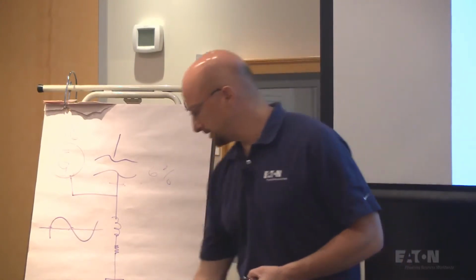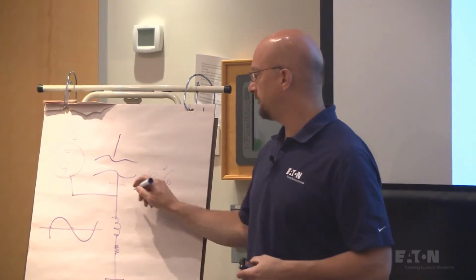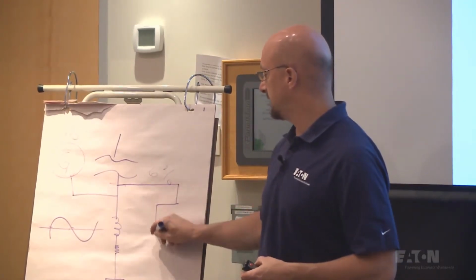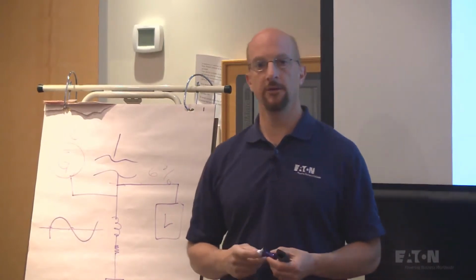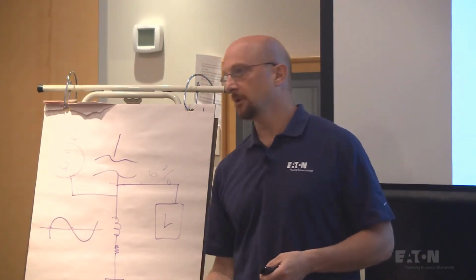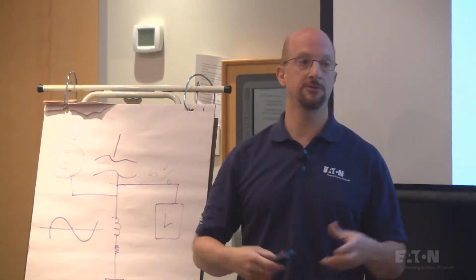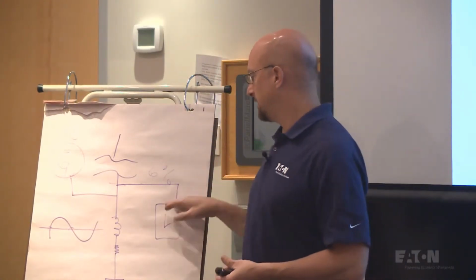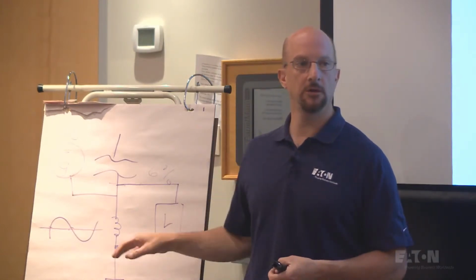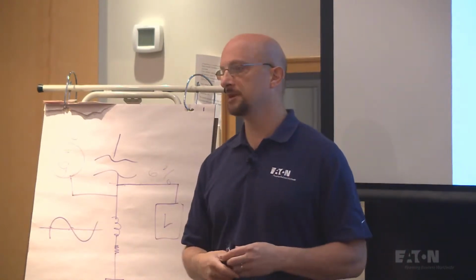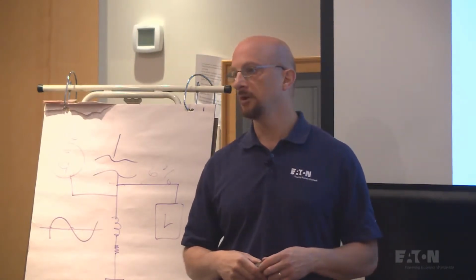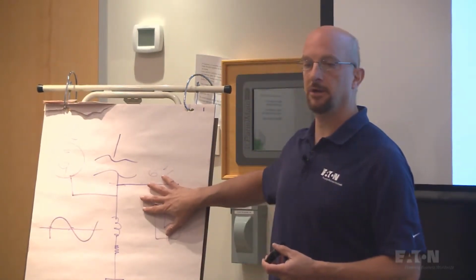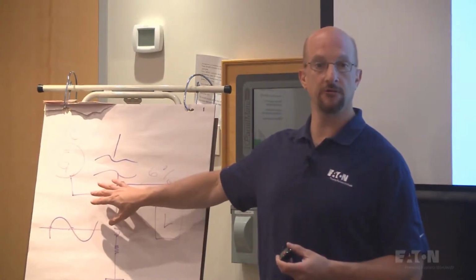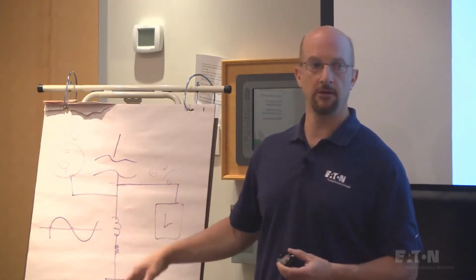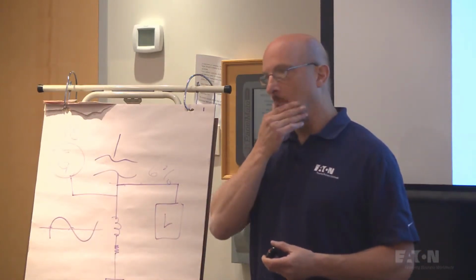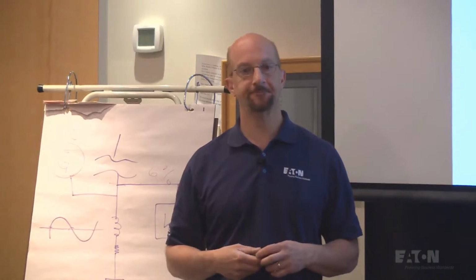The other thing that I will tell you is if you have a whole bunch of drives down here and you're trying to figure out your 519 compliance, make sure you add in a linear load there. Why? Because you are going to have linear load. What's a typical linear load? A whole bunch of motors that are running across the line. That in combination with the harmonic load is going to make your current distortion go down in terms of percentage, and it's going to be more realistic of what you have. If you completely ignore your linear load, your current distortion is going to artificially be higher. Your voltage distortion, by the way, doesn't matter. It's only going to be affected by this. But your current distortion will definitely be different.